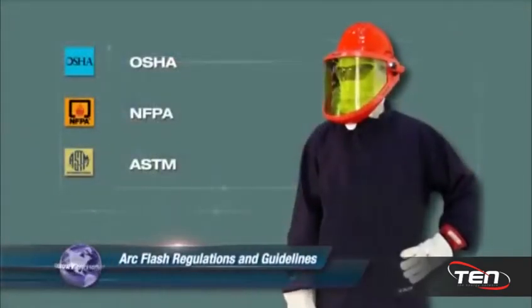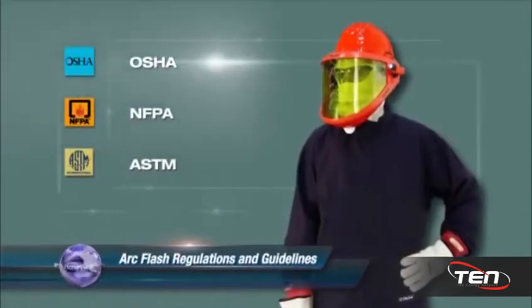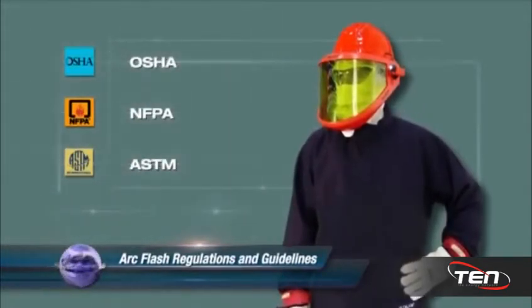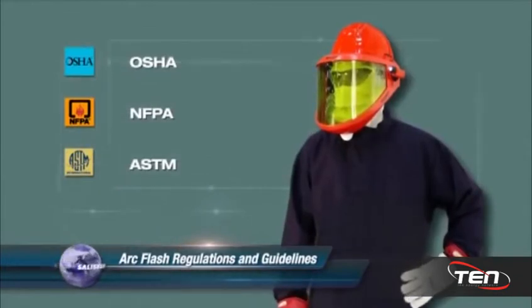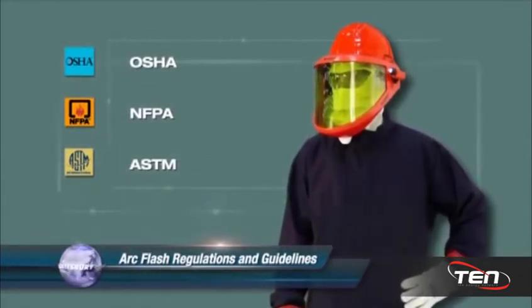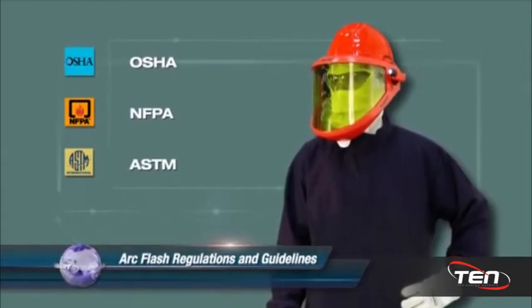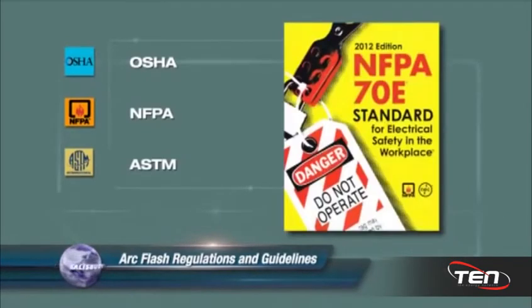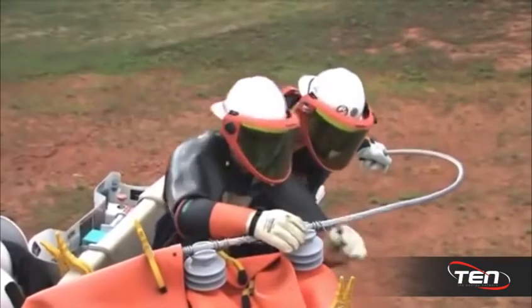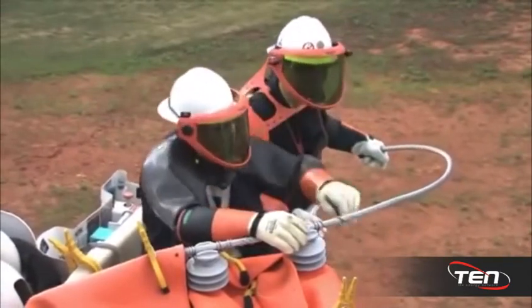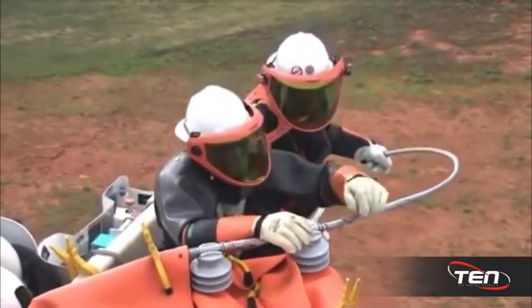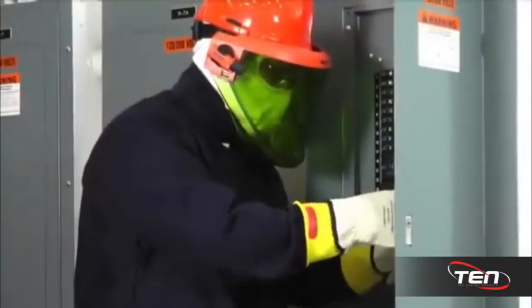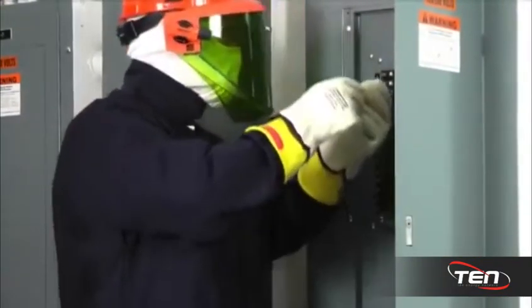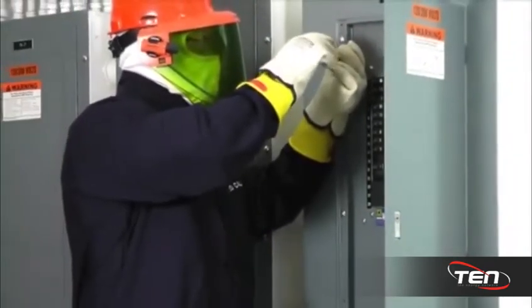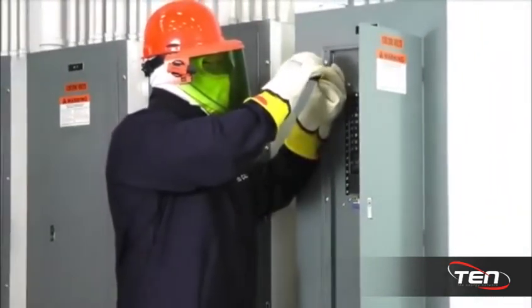To help protect workers from the dangers of arc flash, several groups, including OSHA, the NFPA, and ASTM, directly address the arc flash risk with a series of regulations, specifications, and guidelines for protection of workers exposed to electrical hazards. The NFPA 70E standard is the most complete source for all safety concerns regarding arc flash. Federal OSHA requires the establishment of a program that protects against shock and arc flash when the potential for arc flash is present. OSHA may consider the employer to be in compliance if the electrical safety program is established and the proper PPE is selected based on the NFPA 70E standard.